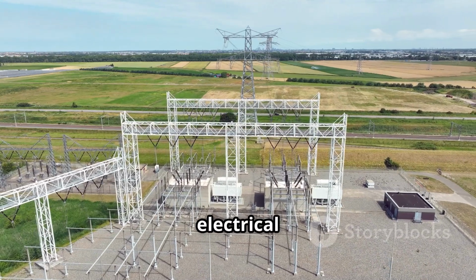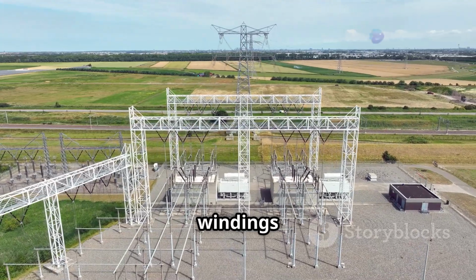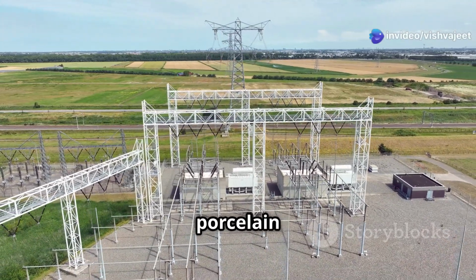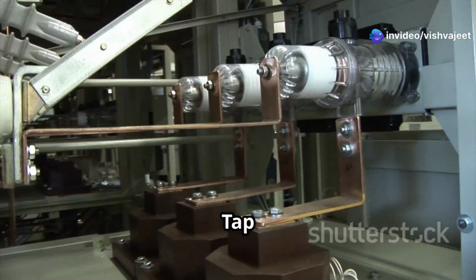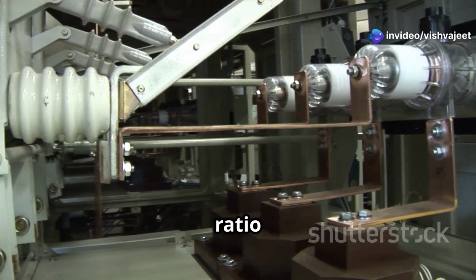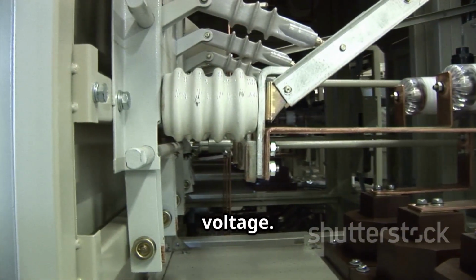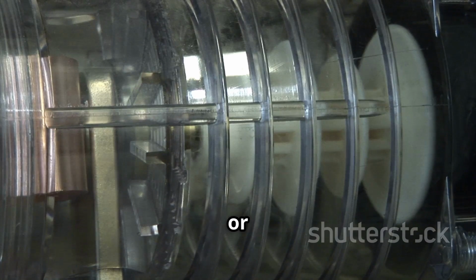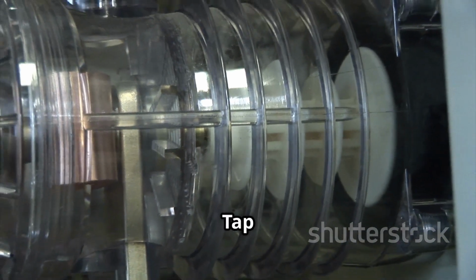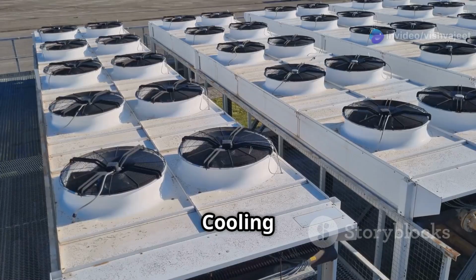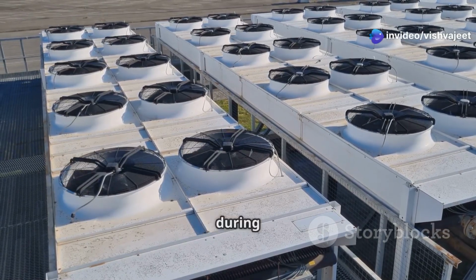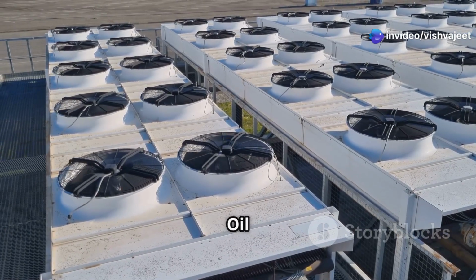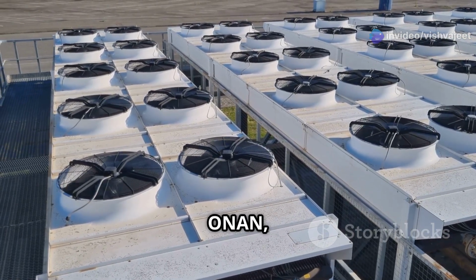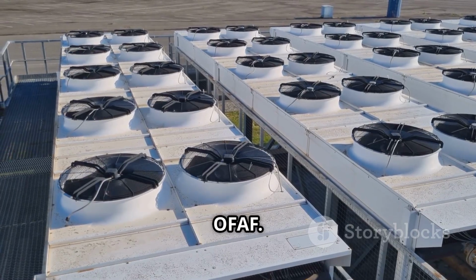Bushings provide electrical connections between the transformer windings and external circuits, made of porcelain or composite materials. Tap changer adjusts the turns ratio to regulate output voltage. Types: on-load tap changer, or OLTC, and off-load tap changer, or DETC. Cooling system dissipates heat generated during operation. Common methods include oil natural air natural, or ONAN, and oil forced air forced, or OFAF.